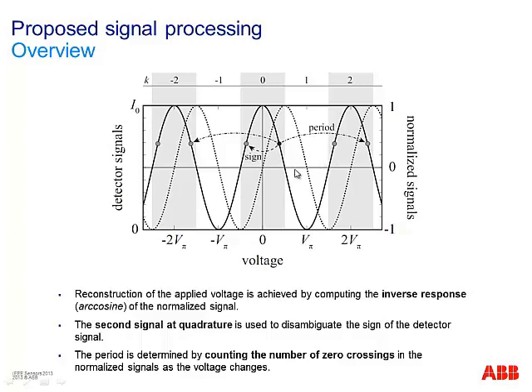Then, to know which period you're on, you count the number of zero crossings you've passed through, because with an AC voltage applied to these sensors, you're really traversing the voltage range on the x-axis, and therefore also the zero crossings of this normalized signal. By counting these, you can determine where you are on your signal.